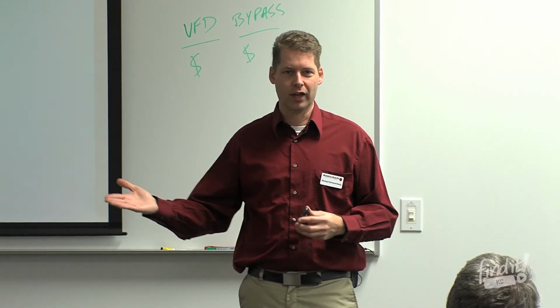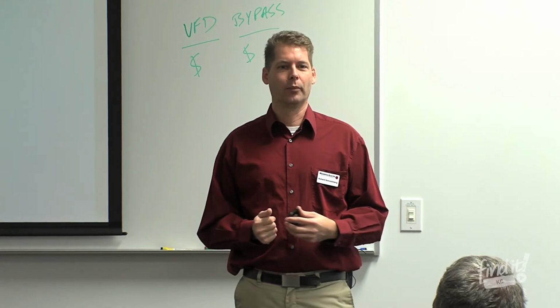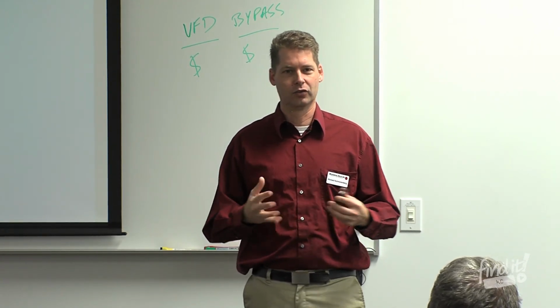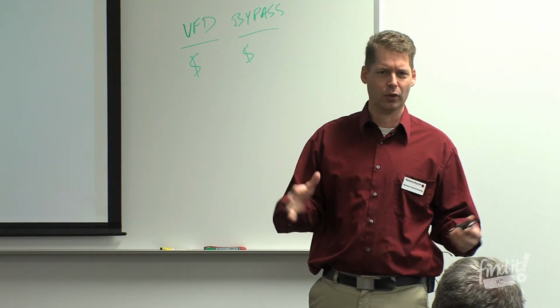So more hours a day may lower the expectancy of the drive's ability to be used. Maybe shortens it a little bit, but not by a substantial amount that anybody's tracked. Another thing that greatly affects the payback is making sure you select a service organization that's trained on the products. It's very, very important. It could take somebody who's not trained an entire day to start a VFD. Someone who is trained should take a couple of hours to do a startup and commissioning. That doesn't include the install time, but the point is that it's very, very critical, from a labor standpoint in your payback, that you're selecting an organization that's trained and ready to do that and does it on a frequent basis.